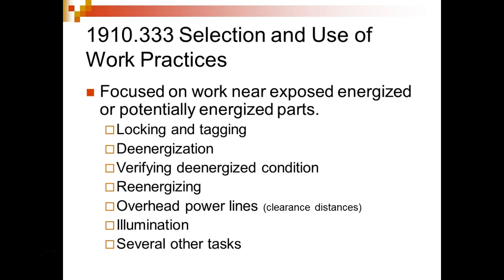Always verify that the energy sources have been dealt with, like we talked about with the pneumatics. Just because I lock and tag my compressor, what do we got to do now? We got to bleed that pressure off, right? With electricity, we've got contacts that get stuck sometimes. So how do we verify there's no electrical energy?